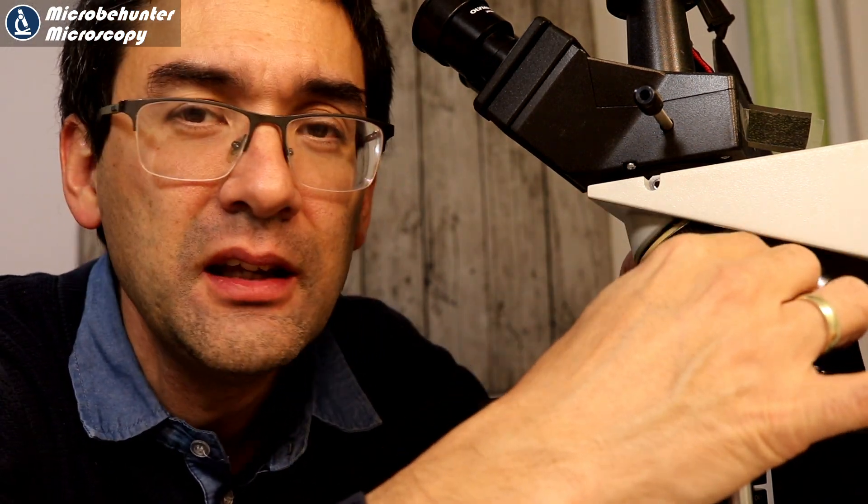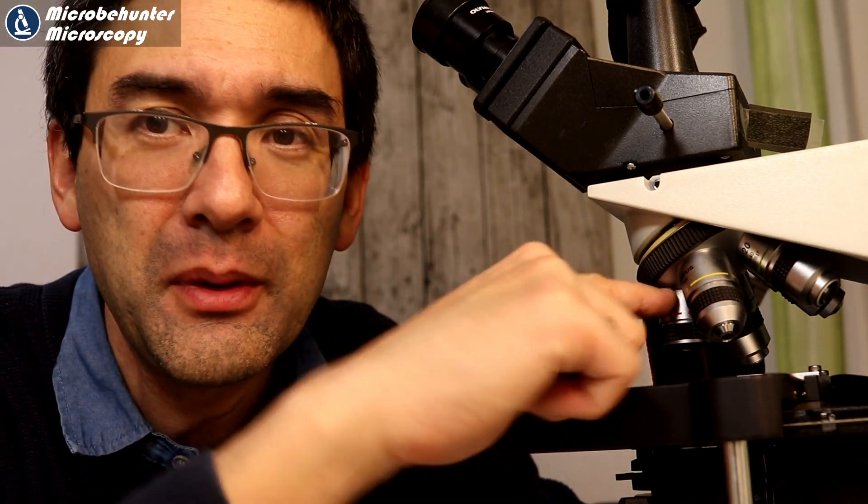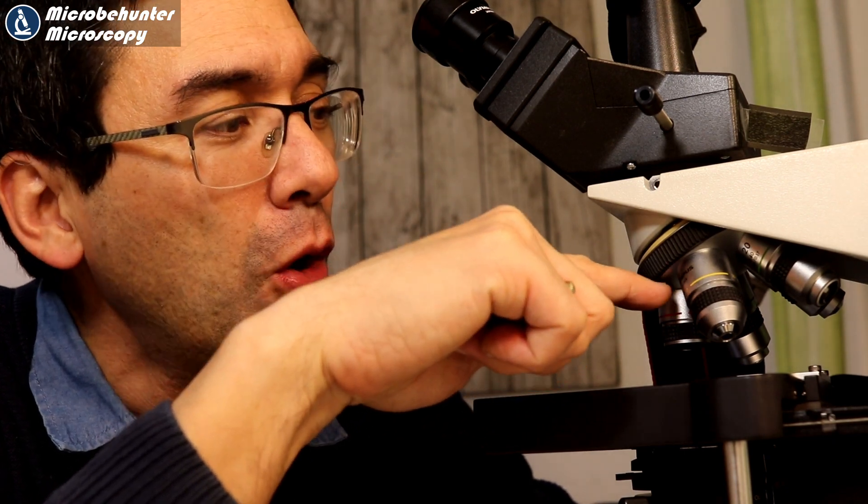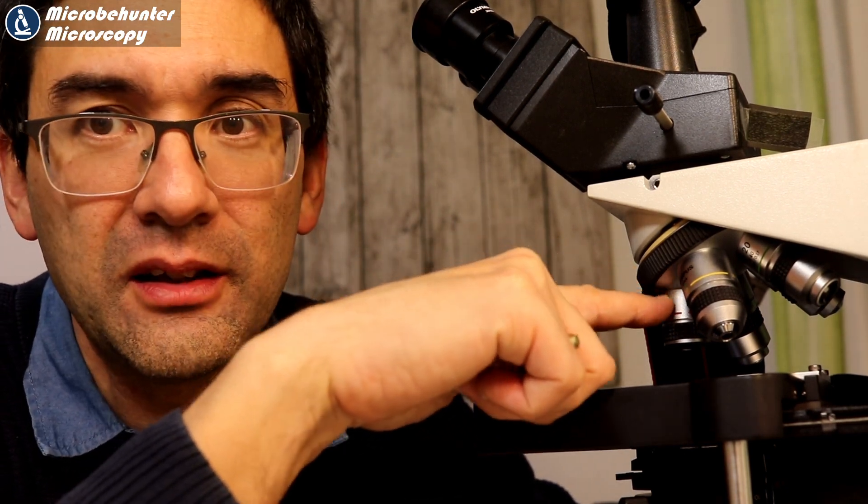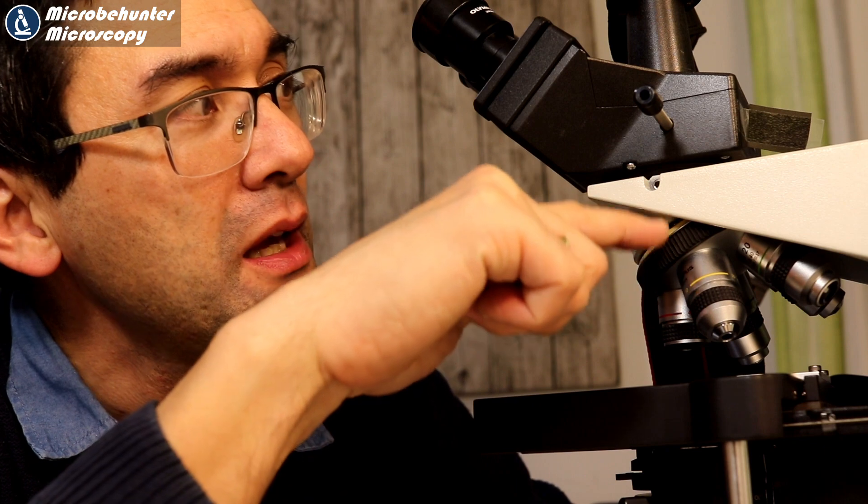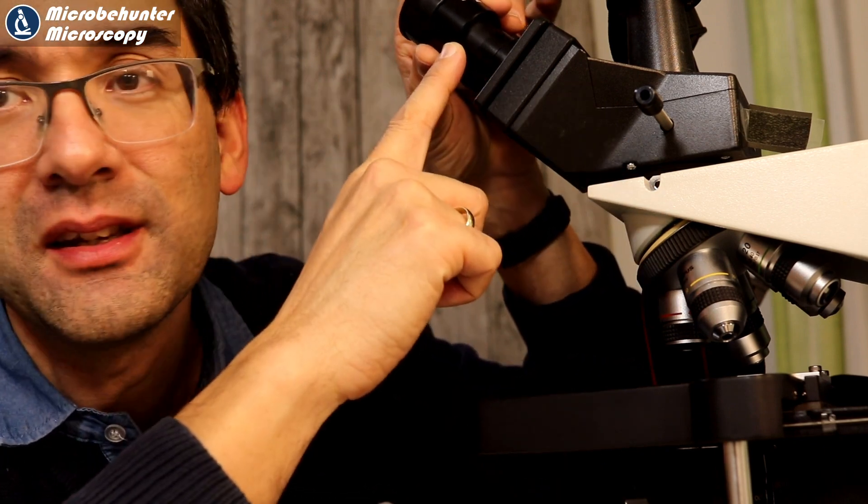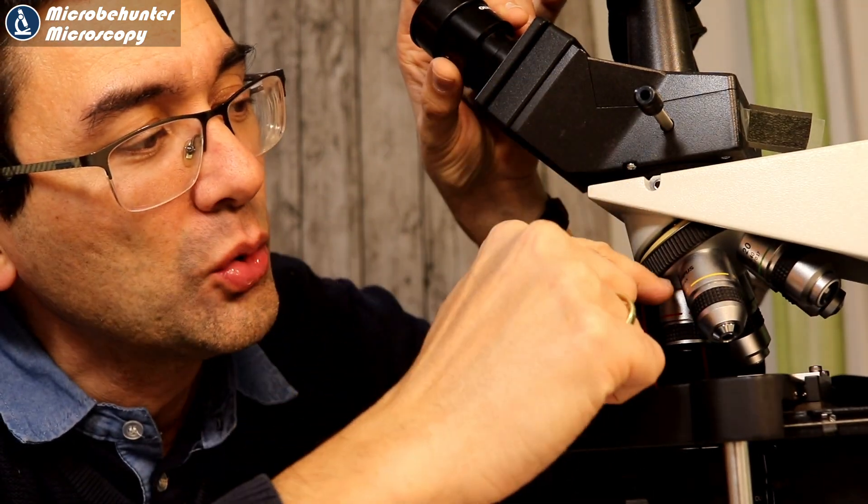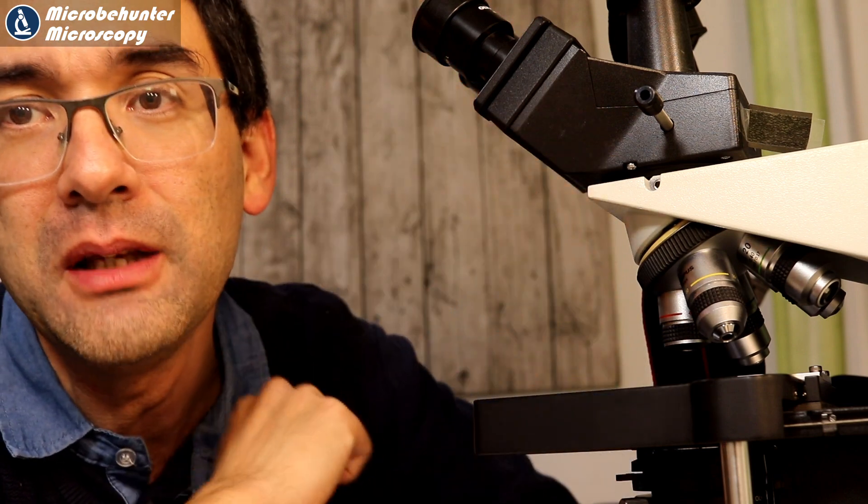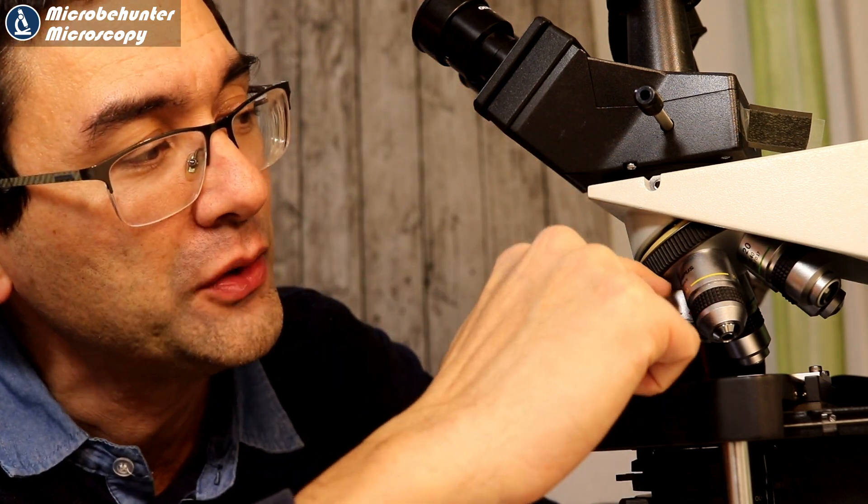This 160 is a very common standard, and this refers to the distance from the microscope objective, where it's connected to the revolving nosepiece, all the way to the place where the eyepiece is. This is the so-called 160 millimeter standard. If you were to measure out the light path all the way up here...